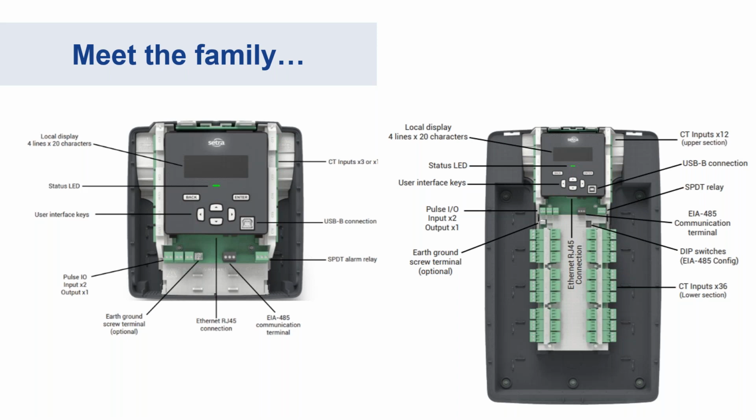But there is a full retention of 62 days of data on the meter itself. So that's really designed around a buffer of an additional month. So if you wanted to pull a month's worth of data, then you'll always have a month's worth as a buffer there in case there's any communications failures with the energy management platform. You can always catch up.